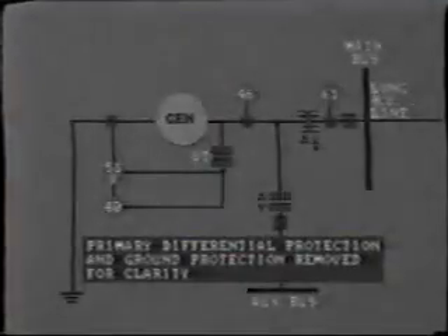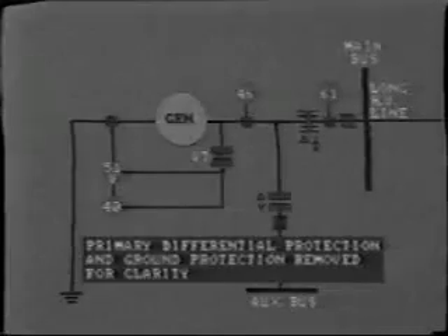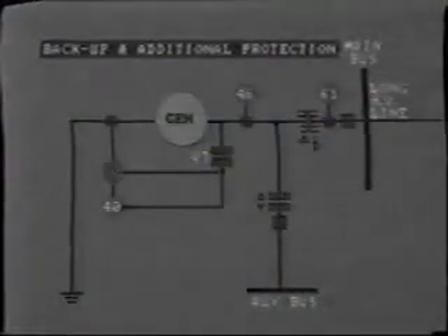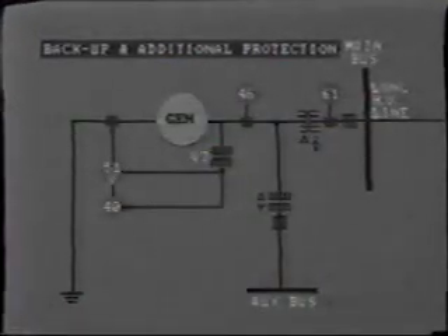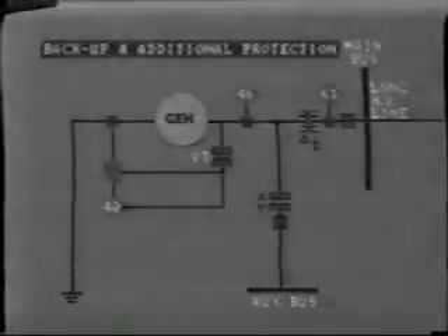Having already discussed primary protection schemes, that is, differential protection and ground protection, for clarity, we have not put them on this diagram. This will allow us to concentrate on backup and additional protection. As with the small generator, we see a negative sequence current relay, a loss of field relay, and a time overcurrent relay with voltage restraint. Quite often, this 51V relay is replaced by a distance relay, device number 21, which is set to reach through the generator and through the unit step-up transformer into the system.